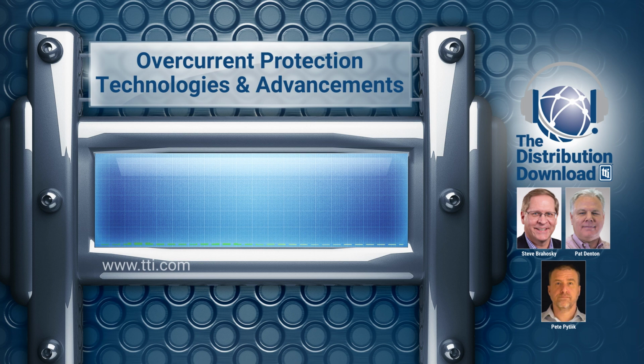In the circuit protection world, there are certain standards like UL that come into play when specifying overcurrent protection. Can you explain the different standards and solutions that Littelfuse has? Sure. So fuses generally fall under two different standards. One is UL, and they'll be generally UL 248. The other one is IEC, and that'll generally be IEC 60127. 95% of the fuses will fall under those two standards.